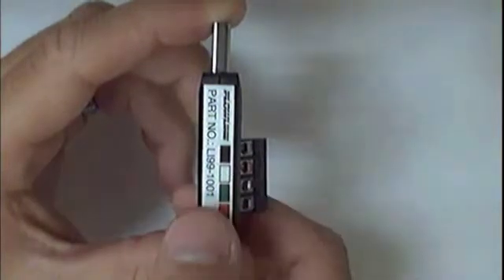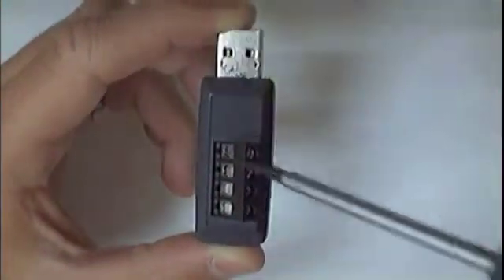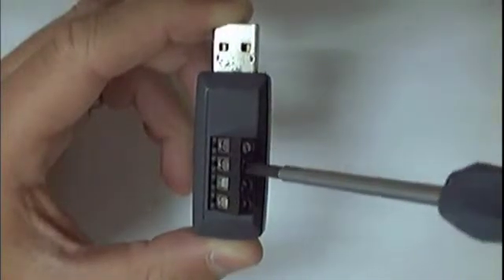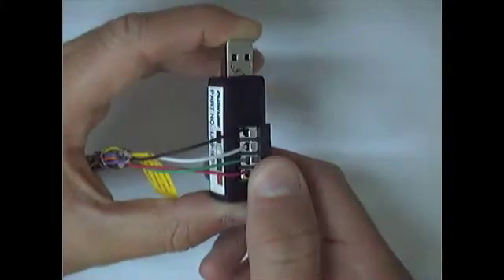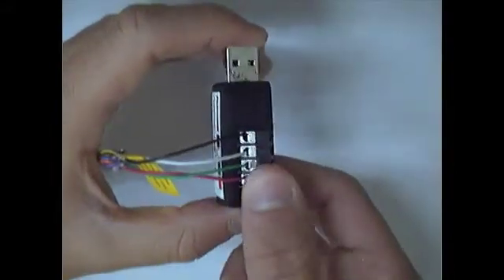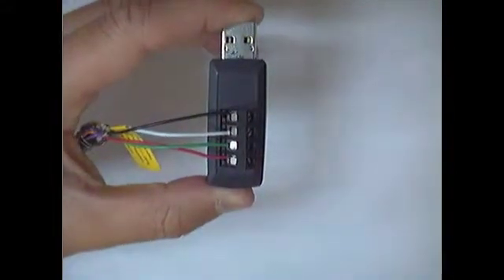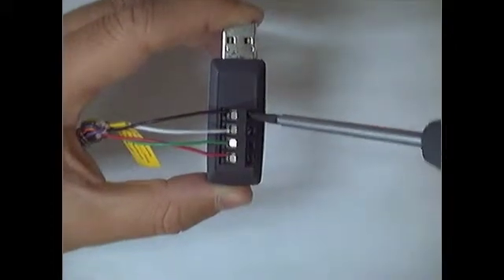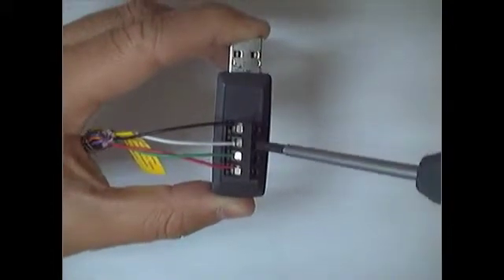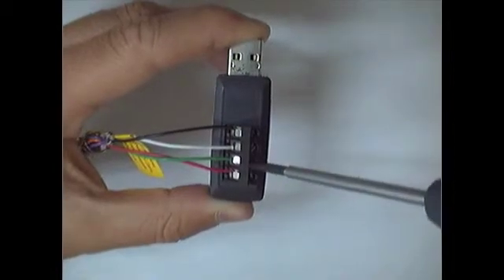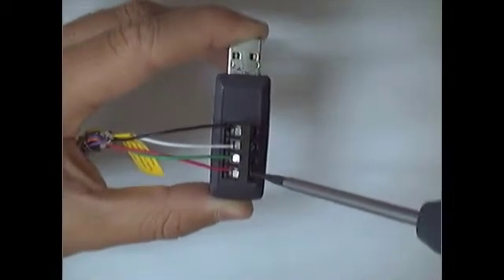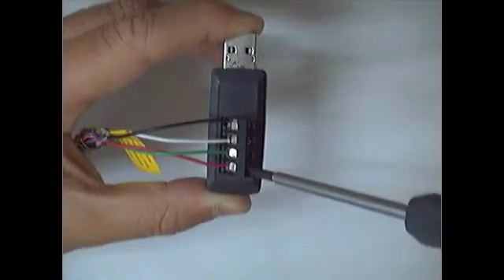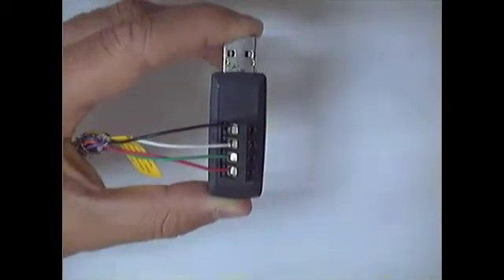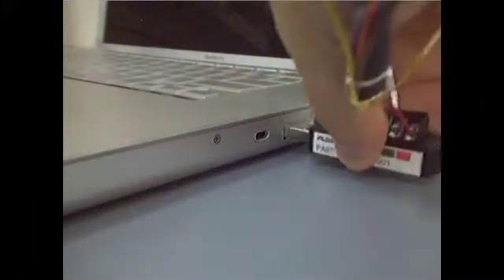After successfully installing WebCal, connect the sensor to the FOB. Turn each screw counterclockwise to open the terminals. Use the color-coded label to line up each color wire from your sensor to the correct terminal. Once each wire has been inserted, turn each screw clockwise to secure the wire. Be sure not to tighten the terminal on the insulation of the wire, as it may cause communication problems during configuration. Insert the FOB into your computer and open WebCal.